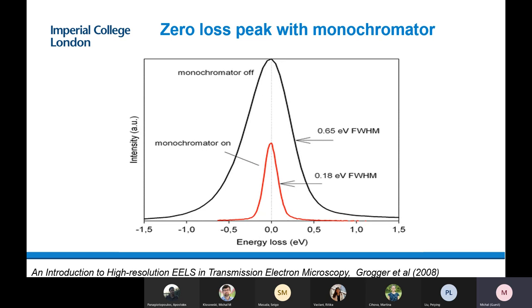There is a defined width for the peak which defines our resolution. We have an instrument on the Titan called a monochromator, which is basically a filter that filters out electrons at different energies at the very top of the column, when the electrons are produced. By using the monochromator, we can reduce the width of the peak, thereby increasing the resolution of our system. However, we are losing some electrons in the process, so the peaks will be less intense and the intensity of our spectra will be reduced.